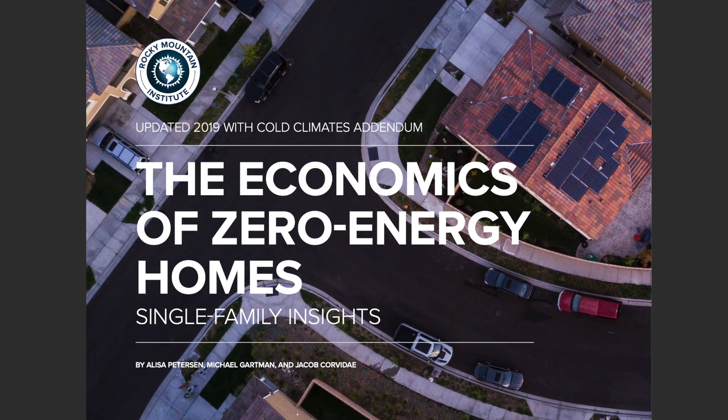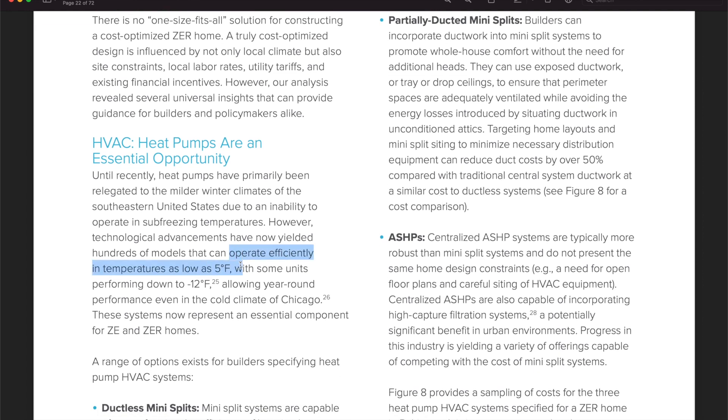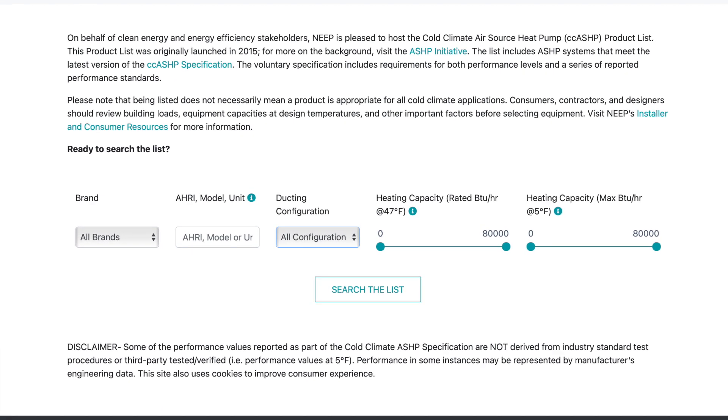So what about the common myths? One of my favorites is that they don't work in cold climates. Cold climate air source heat pumps are specifically designed for this, featuring a built-in inverter-driven compressor and refrigerant unit that works excellently in icy climates. In 2019, the Rocky Mountain Institute stated that hundreds of models can operate efficiently in temperatures as low as 5°F (about -15°C), with some units performing down to -12°F (about -24°C). To check if a unit qualifies as cold climate, see the Northeast Energy Efficiency Partnership's database linked in the description.